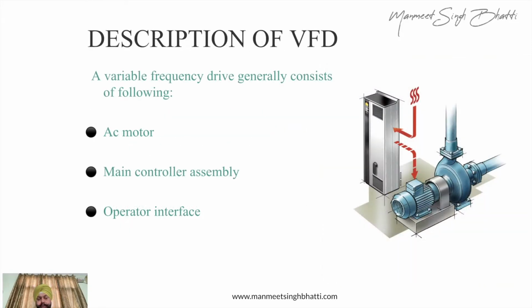Now, how do you explain what kind of drive it is? The main component of this system is, first, the AC motor. As you can see, the AC motor is going to provide the mechanical energy. Then in the VFD, we have the main controller assembly, which does the control of the power. If you see on the right hand side, there is a complete architecture. The power comes from the top, or you can say the incomer to the VFD, and then it is controlled based on the need, and then it is fed to the motor.